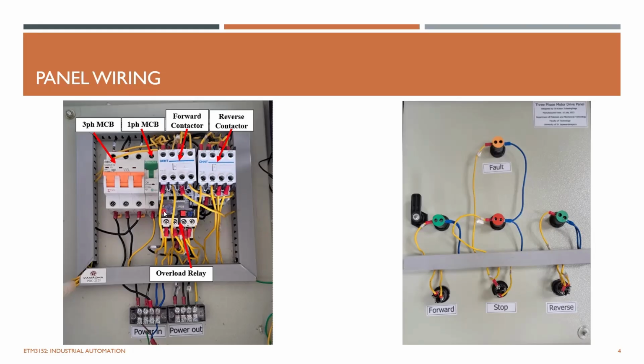This is the thermal overload relay. If a thermal overcurrent event happens, this will disconnect the power to the power out terminal. You can manually trigger it, and this blue colored one is to adjust the triggering current. So you can select 2 ampere, 4 ampere, or 6 ampere, depending upon the selected thermal overload relay.